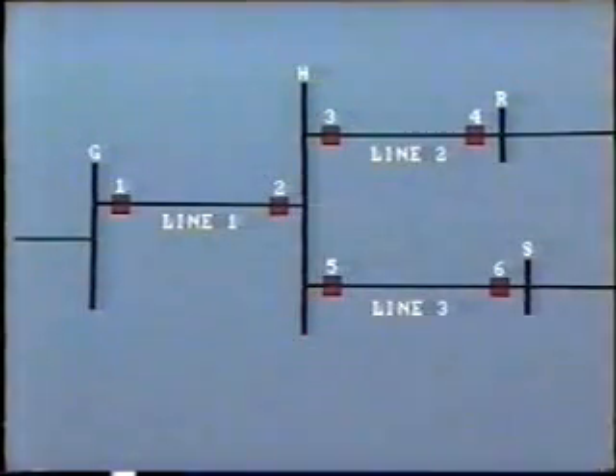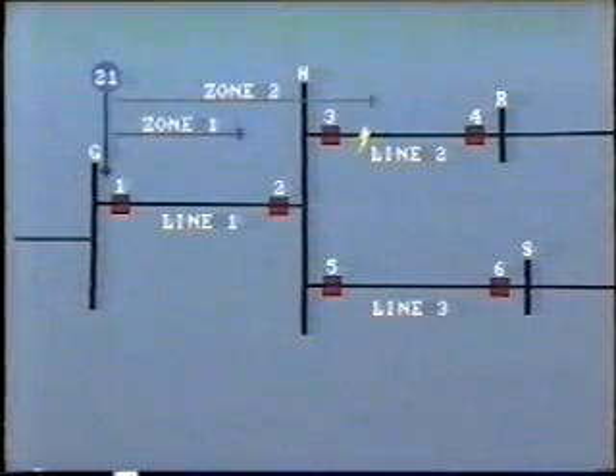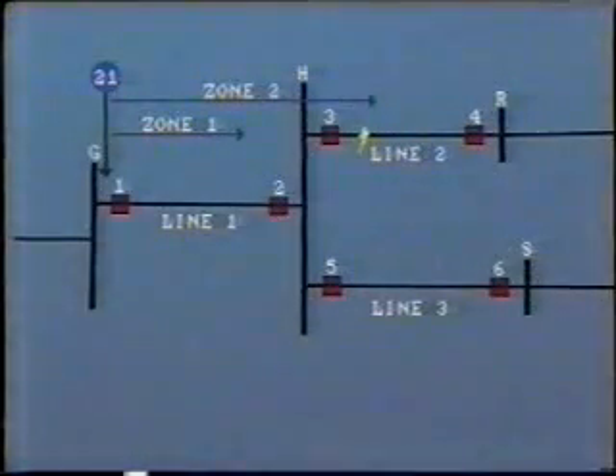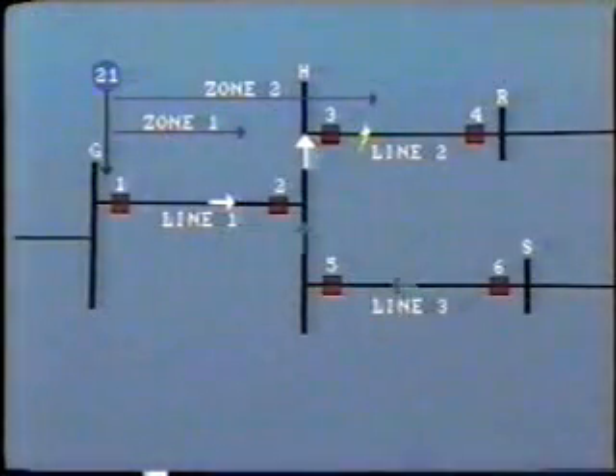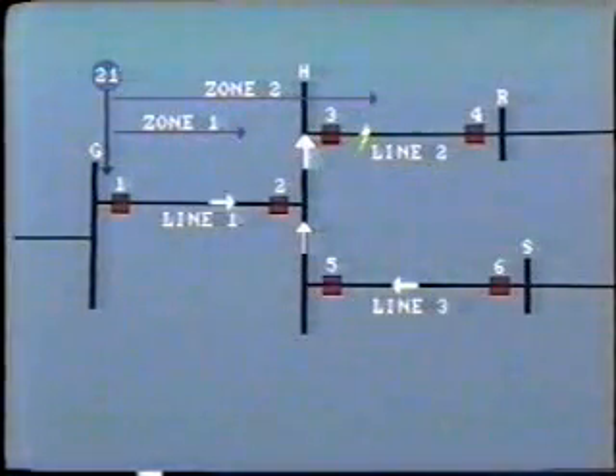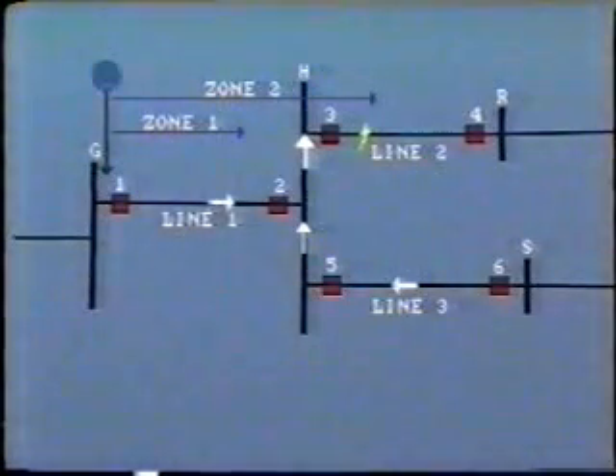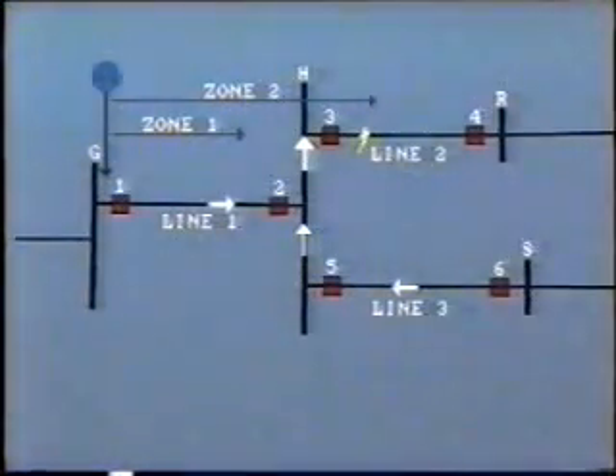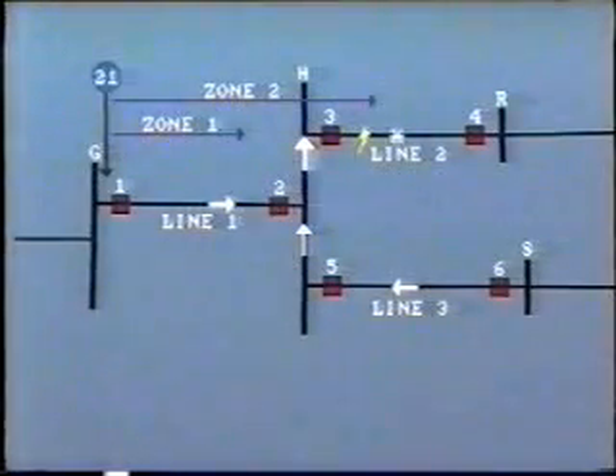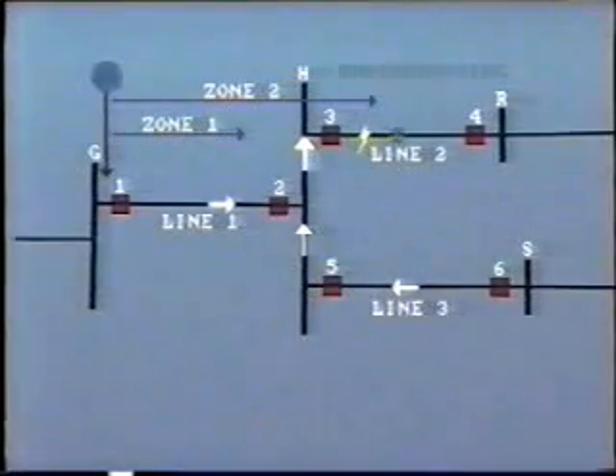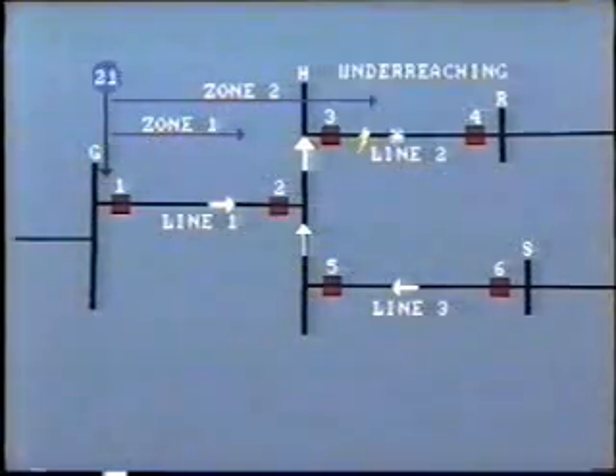Let's now look at the case where there is a fault, say 20% along line 2. This just falls within the protection area of zone 2 of the distance relay at bus G. However, in this situation, current is also feeding into the fault from line 3, as there is a power source connected. The result is that slightly less current will flow along line 1 to feed the fault. So the impedance relay will sense that the fault is of higher apparent impedance and therefore farther out along the line, probably outside of the zone 2. Therefore, this relay would no longer provide backup for this particular fault. This condition is known as underreaching. The relay thinks that the fault is farther out and beyond its reach, and it does not operate.